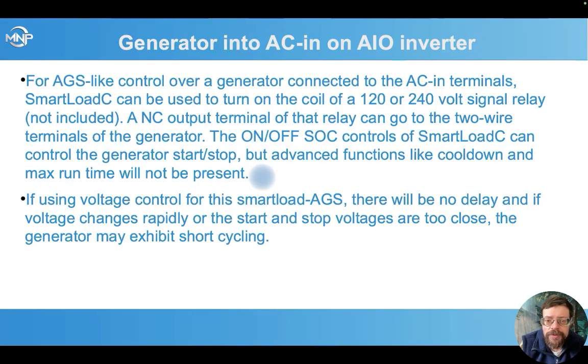There is a way that you can get some control over a generator connected to the AC in terminals for automatic starting and stopping. And this is to use the smart load C, that's your 30 amp smart load, to go to the coil of a signal relay and then connect an output terminal of that relay to the 2-wire start terminals of the generator. So by controlling when that smart load C turns on and off, you essentially start and stop that generator. You won't have the advanced functions, but it can do that. And remember that in this case, you're not going to have any delay or things like that. So make sure you've got your voltages or state of charge settings far enough apart that you don't have short cycling of your generator.